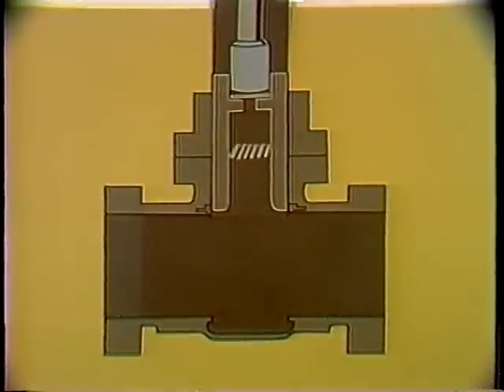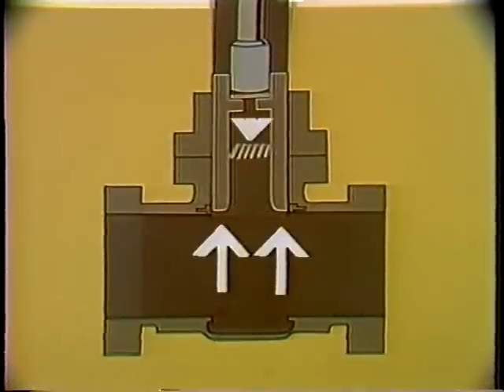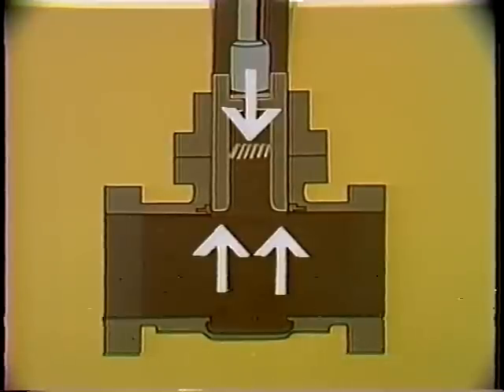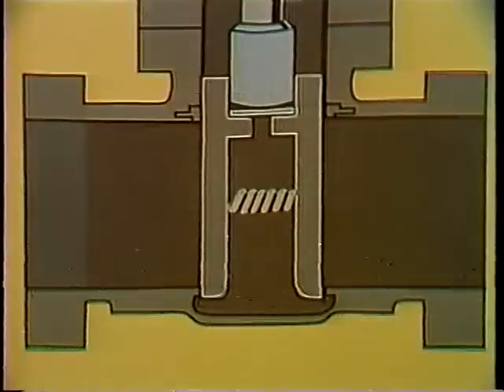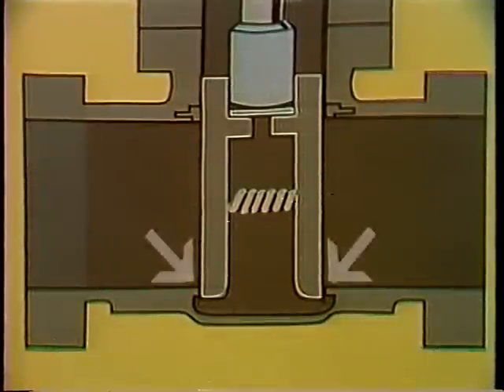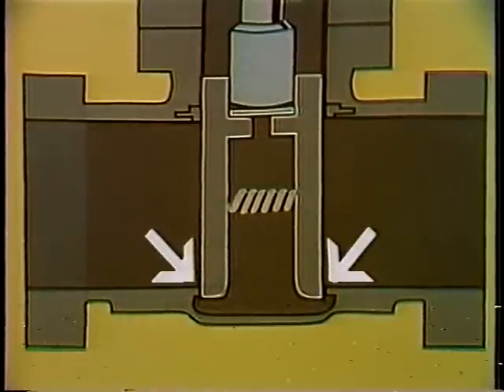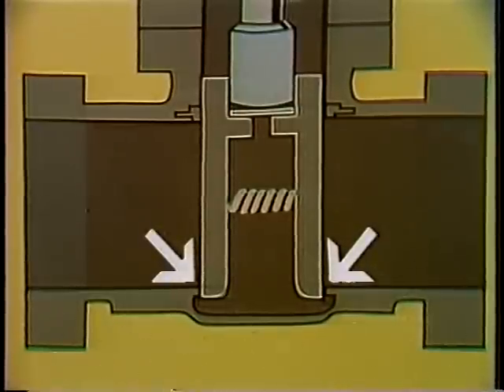The double disk type is made of two separate disks with a spring mechanism between them. The spring holds each disk in place against its seat while the valve is being operated. When the double disk is lowered, there is no wedging or jamming action as it closes over the seat. This feature makes the double disk particularly adaptable to motor operating mechanisms, such as steam stop valves.